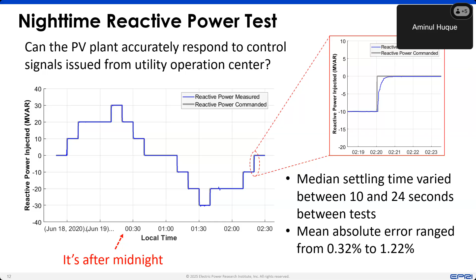So what we have seen is that yes, there is some delay once you issue the command. Depending on which value and which direction we are asking the plant to provide reactive power support, the response time was between 10 seconds and 24 seconds. And remember, the command was issued to the plant controller, and then the plant controller was issuing the command to the inverter. So of course, there are some communication delays there, but roughly between 20 to 24 seconds were needed for the settling time. And in terms of accuracy, the error was somewhere between 0.3% and 1.2% compared to target values and what was actually absorbed or injected by the plant. So that's the first level of verification: can it do it or not?